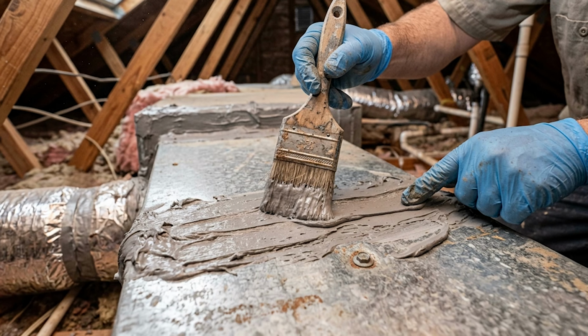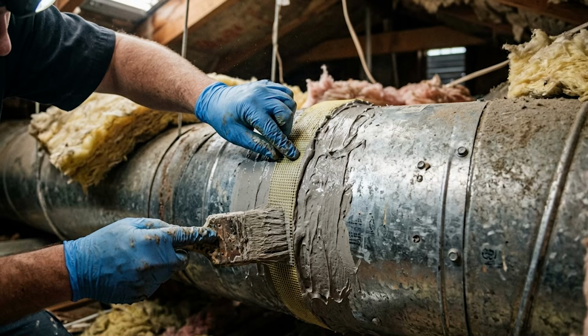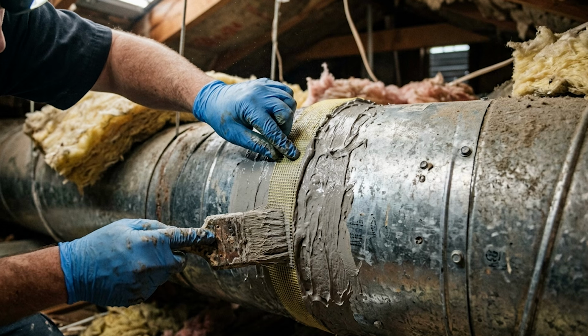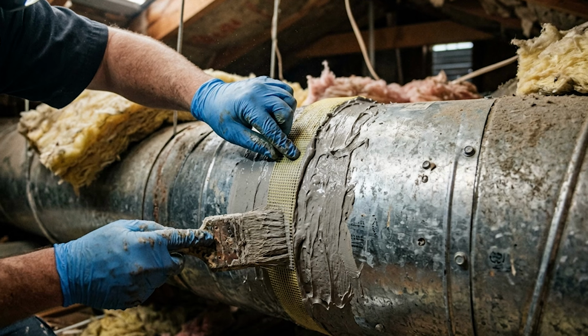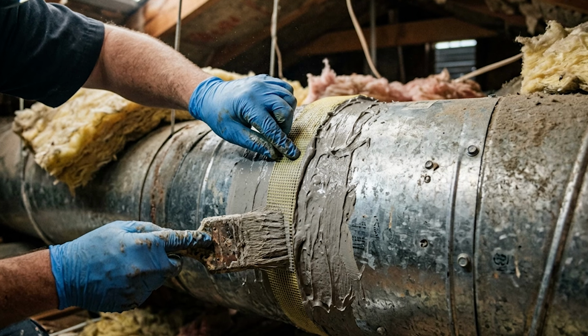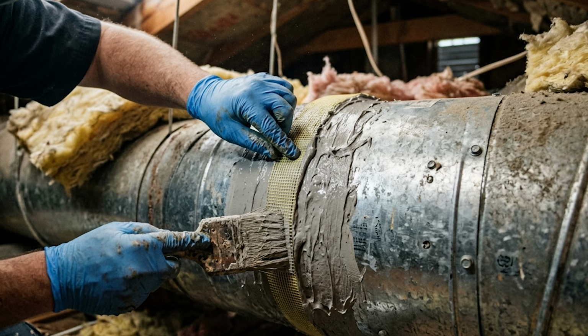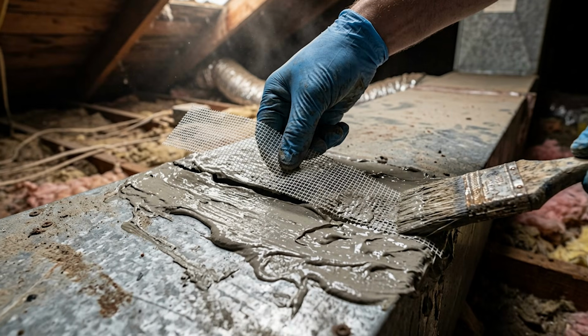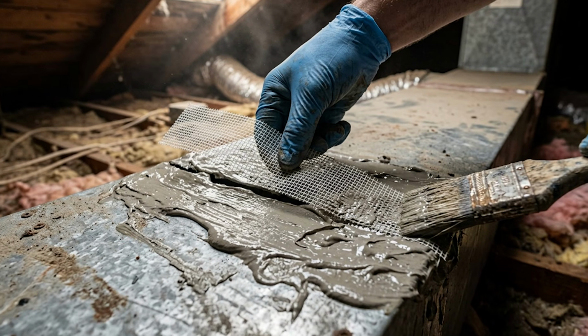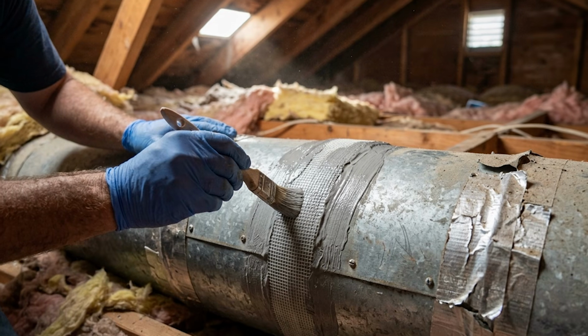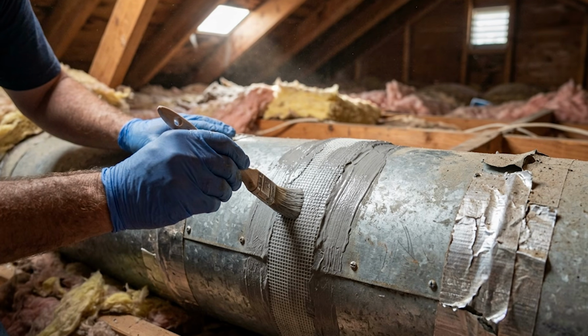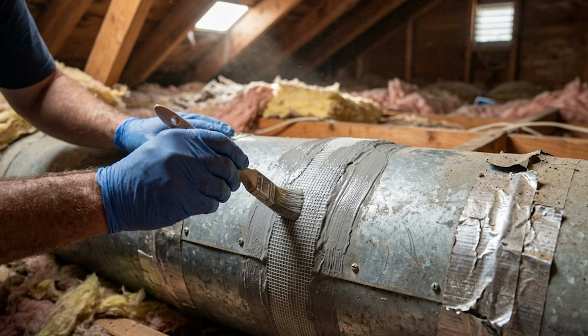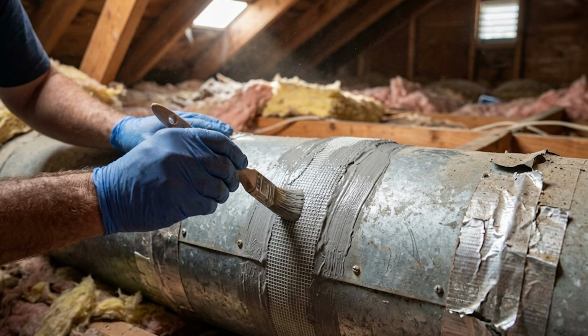For any gap larger than about a 1/4 inch, do what professional HVAC technicians do. Embed a piece of fiberglass mesh tape into the wet mastic. Then apply a second coat of mastic over the top of the mesh. The mesh gives the sealant something to bond to across the wider gap and prevents cracking over time. Almost no consumer video shows this step, but it is how the professionals do it. And it is the difference between a repair that lasts and one that fails in a few years.